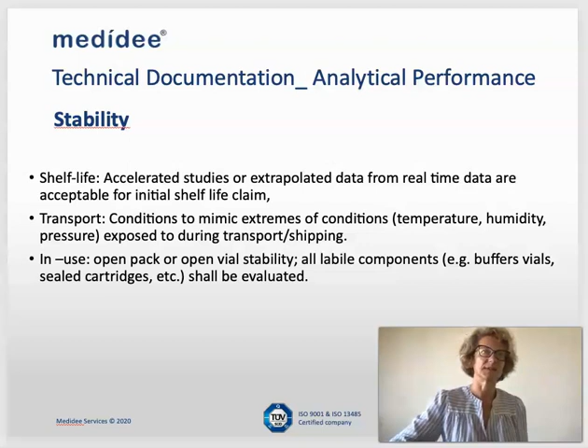And also for lateral flow test, we can ask the question, well, what happens if we open the pouches? Normally lateral flow tests come individually in aluminum pouches, because lateral flows are known as being sensitive to humidity. So one other question would be, what happens if the seal is open? How long can I keep the test before performing it? This kind of study is done during these stability activities.